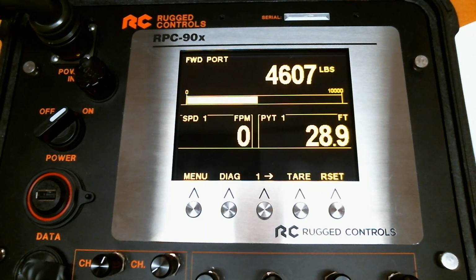For the mathematical approach, we would need to calculate the pitch diameter of the sheave in question that has the targets on it, which is the root diameter of the sheave plus one wire rope diameter, and calculate circumference with that diameter. And we'd also need to determine the number of pulses or targets per revolution. We will need to calculate pulses per unit length, and we will be using that scalar as the calibration coefficient for payout and scale for that sensor.